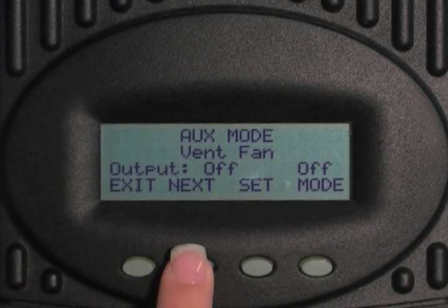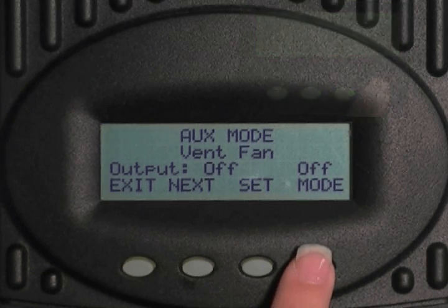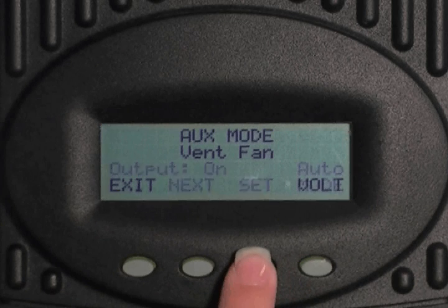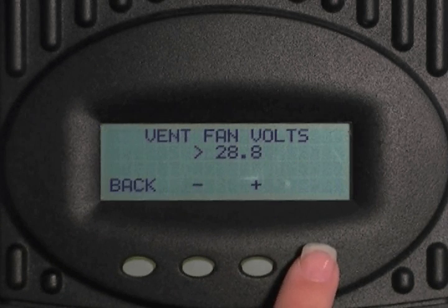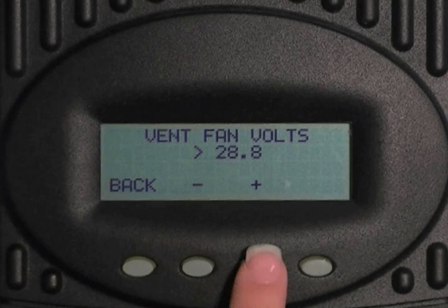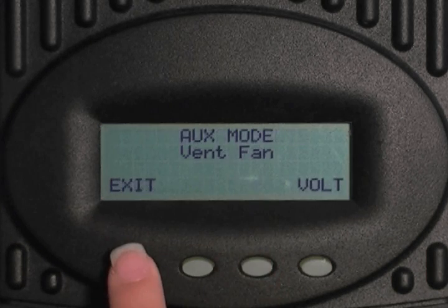Press mode. Select the minus key to bring the password down to 141 and press enter. Press mode to change the output from off to on to auto. Now select set. Select volt. This is the voltage set point when your vent fan will turn on and must get less than in order to turn off. Press the minus or plus keys to adjust this setting. Press back, then press exit.